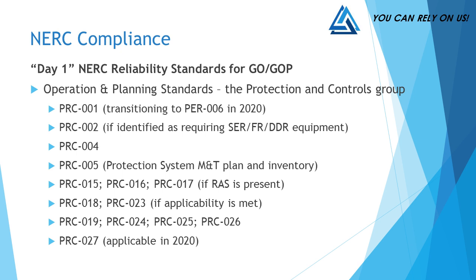Then there are a couple of groupings, only applicable if you have very particular types of protection systems. RAS is a remedial action scheme, not that common for smaller utilities. There are a couple of PRC standards only applicable under certain conditions. The grouping for PRC19, 24, 25, and 26 requires extensive evaluations of your protection system settings—how they're set up and coordinated with your generation—requiring significant engineering analysis.